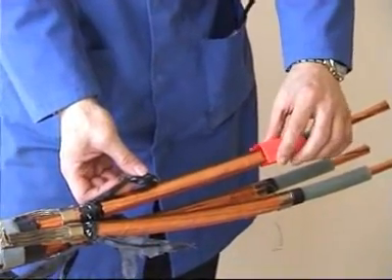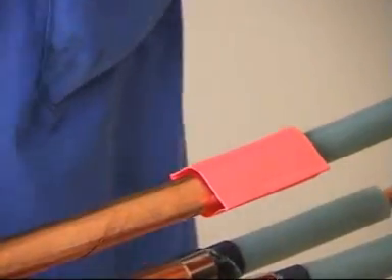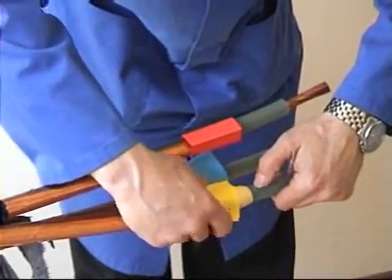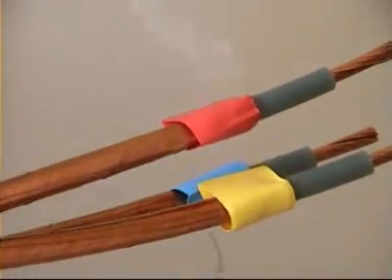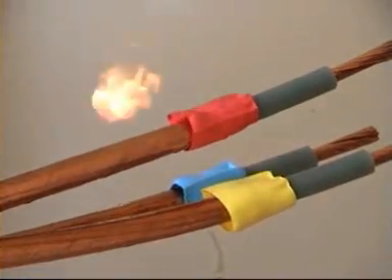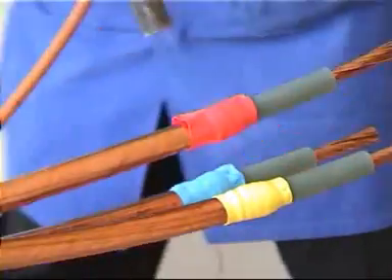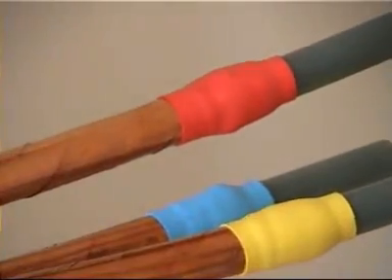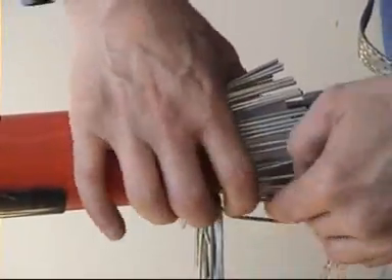Now position the short lengths of coloured heat shrink sleeve which protects the tape at the end of the screen cut and also acts as a useful phase marker. Apply tape to the remaining screen cuts and position the other phase markers. With a suitable heat source, shrink these down, keeping the flame on the move all around the sleeves.